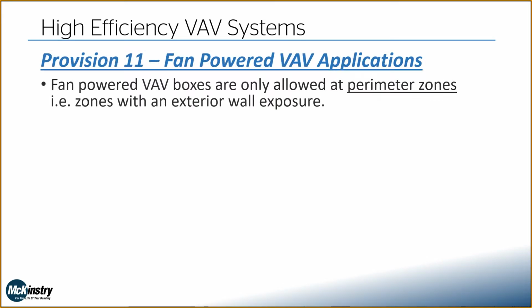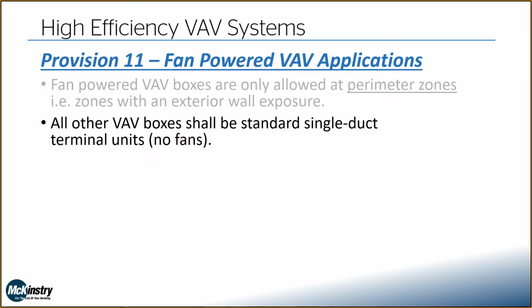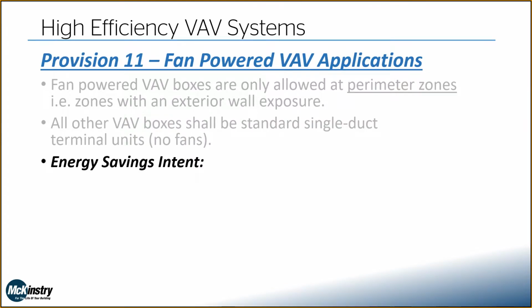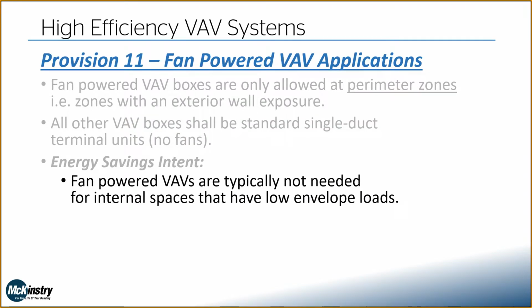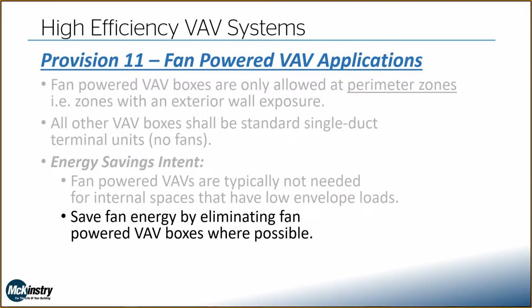Fan-powered VAV applications. We can only use fan-powered VAV boxes at our perimeter zones, zones with an exterior wall exposure. All other VAV boxes on that project shall be standard single duct terminal units, so they won't have any fans. The intent here: typically we don't need fan-powered VAVs for our internal spaces that have really low envelope loads. Typically they're just not necessary. So let's save some fan energy and get rid of fan-powered VAV boxes wherever we can.